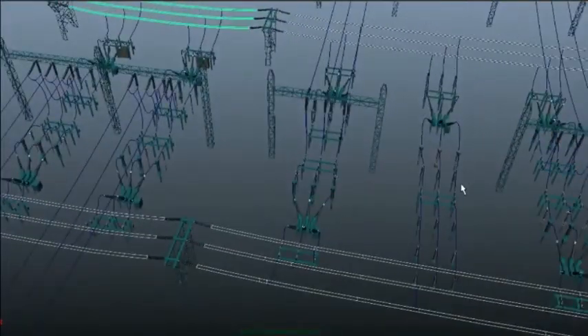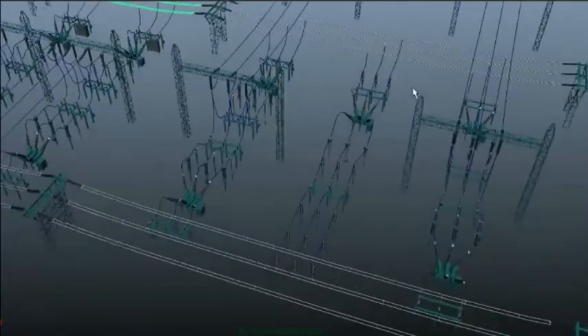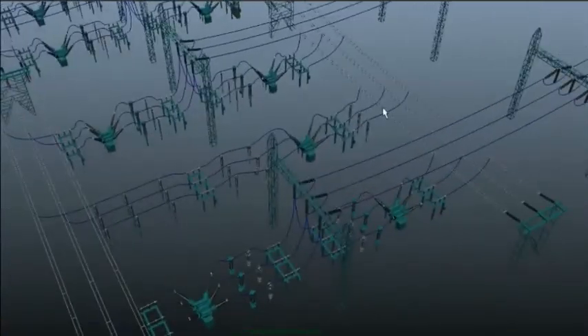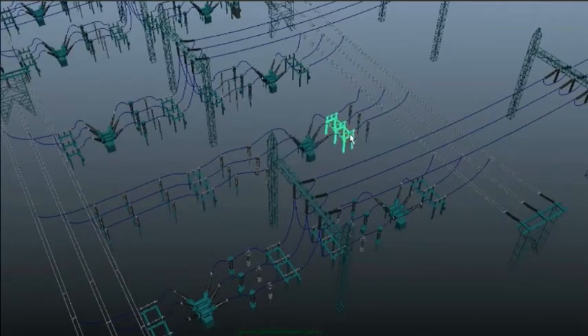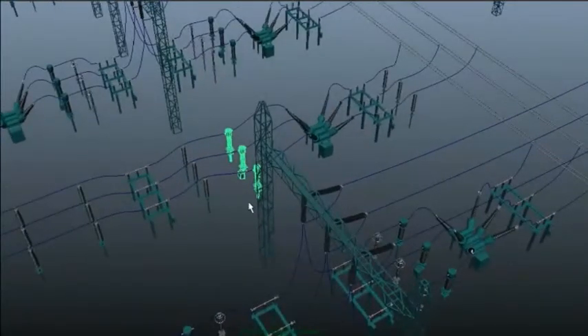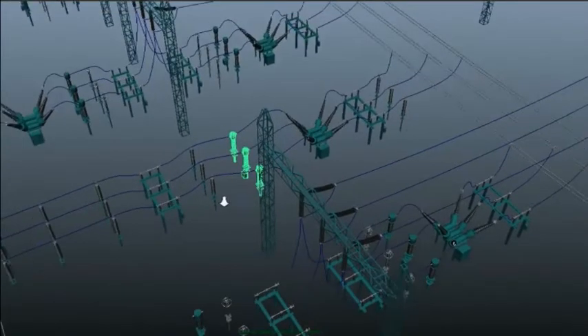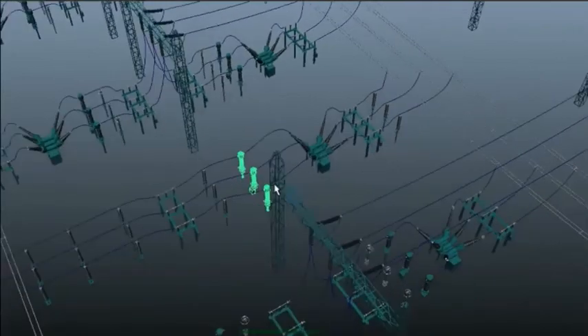There is a bus coupler between these 2 buses which helps to couple both the buses electrically. It consists of a circuit breaker and isolator on either side, which are used to isolate the circuit breaker during the maintenance. Current transformers are installed in bus coupler to measure how much current is flowing from bus 1 to bus 2 and from bus 2 to bus 1.